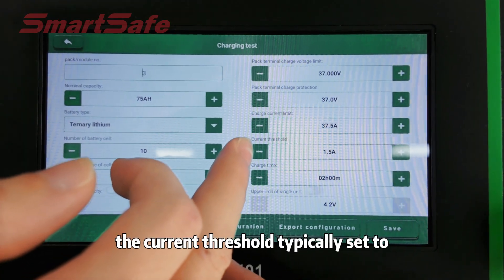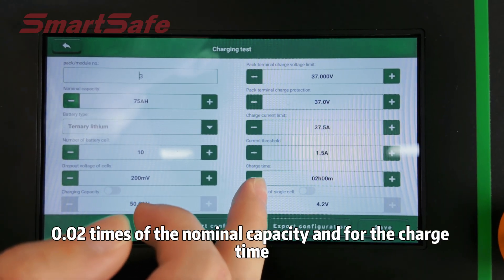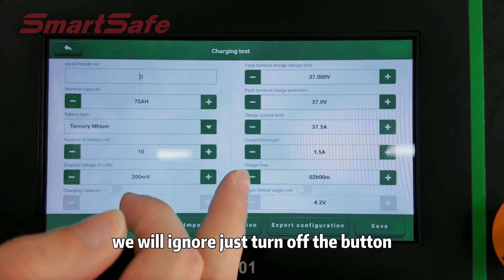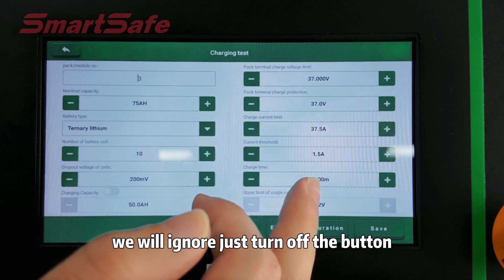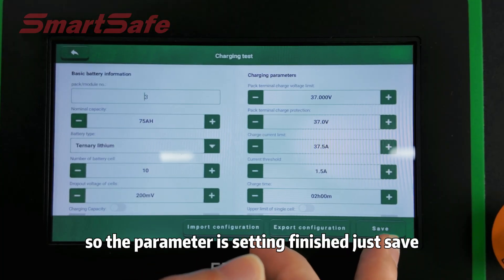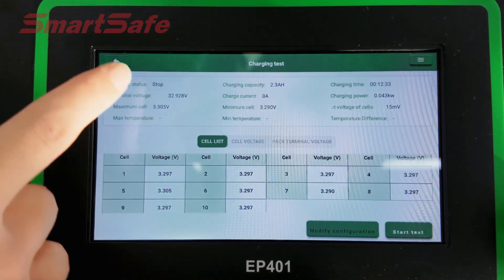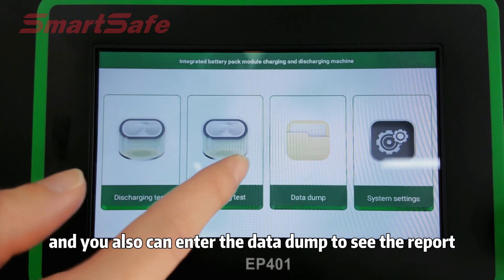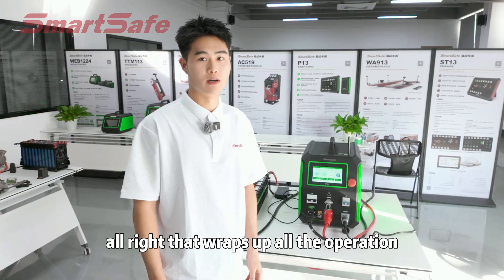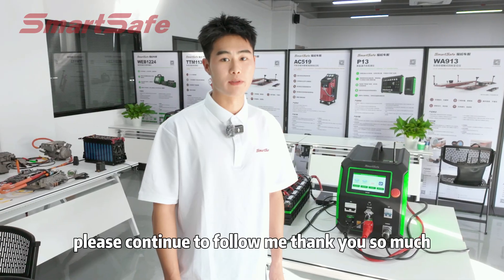For the current threshold, it is typically set to 0.02 times the nominal capacity. For the charge type, we will ignore it — just turn off the button. The parameter setting is finished. Save, and the charge test process will begin. You can also enter the data dump to see the report. That covers all the operations. If you want to know more about product reviews, please continue to follow me. Thank you so much.